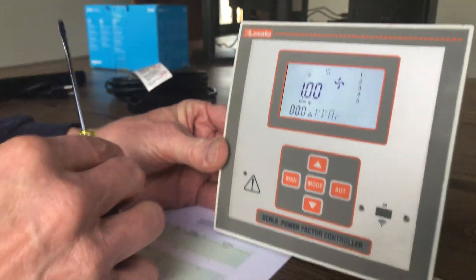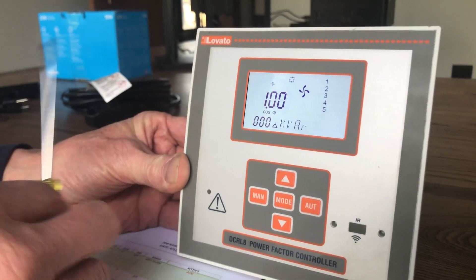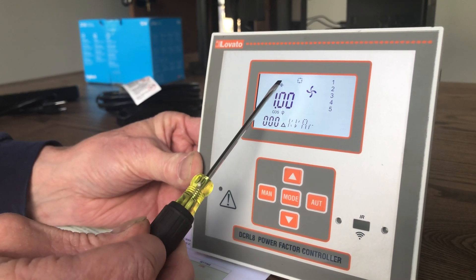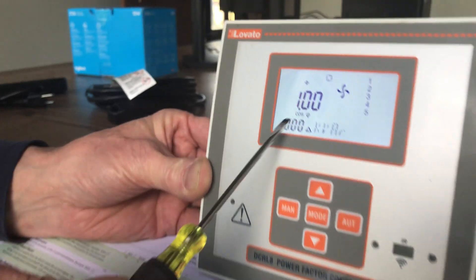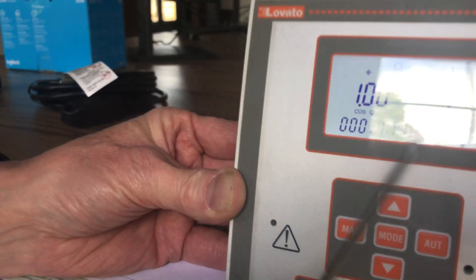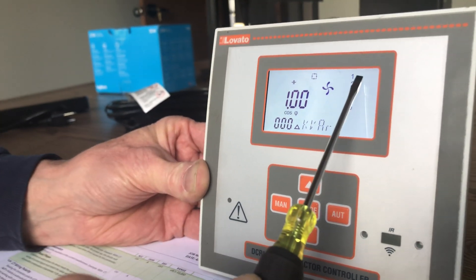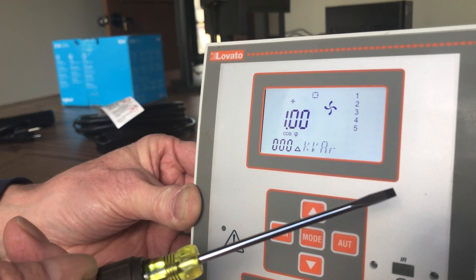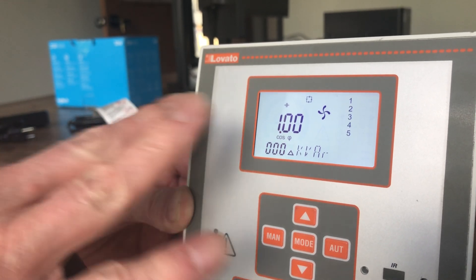So initially, if the controller is operational and your bank is up and running, this is the display you might see. It'll show you the current power factor, whether it's capacitive or inductive. It'll show you the delta kVAR, which is the amount of VARs required to get to your target power factor. So if your target power factor is unity, this would be the VARs on your bus. Over on the right, it shows you the number of steps programmed into the meter, which reflects what you have installed on your equipment, and it'll give the status of each step. This is automatic mode — this is how it would be running.